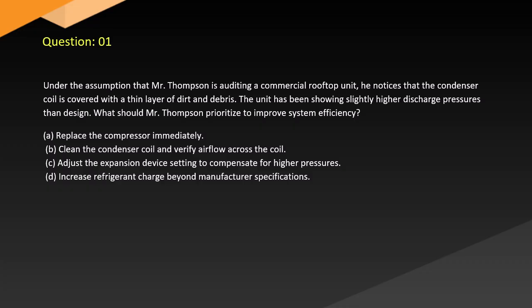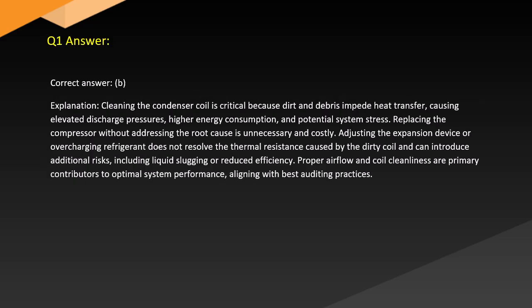A. Replace the compressor immediately. B. Clean the condenser coil and verify airflow across the coil. C. Adjust the expansion device setting to compensate for higher pressures. D. Increase refrigerant charge beyond manufacturer specifications. Answer. Correct answer: B. Explanation.